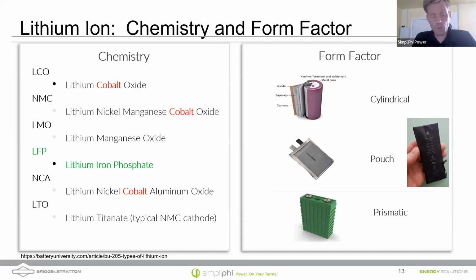So when you charge and discharge a battery, it heats up, and that amount of heat causes thermal expansion. And if those batteries get too hot, that thermal expansion can cause separation of layers and other problems, breakdown of chemistry inside the batteries. And so prismatic cells don't last quite as long as cylindrical cells, but they tend to be a little bit cheaper.